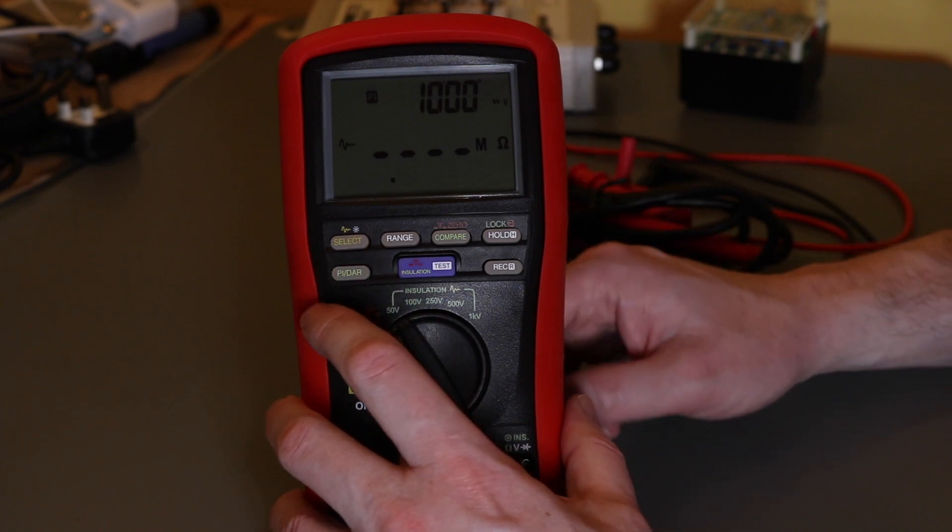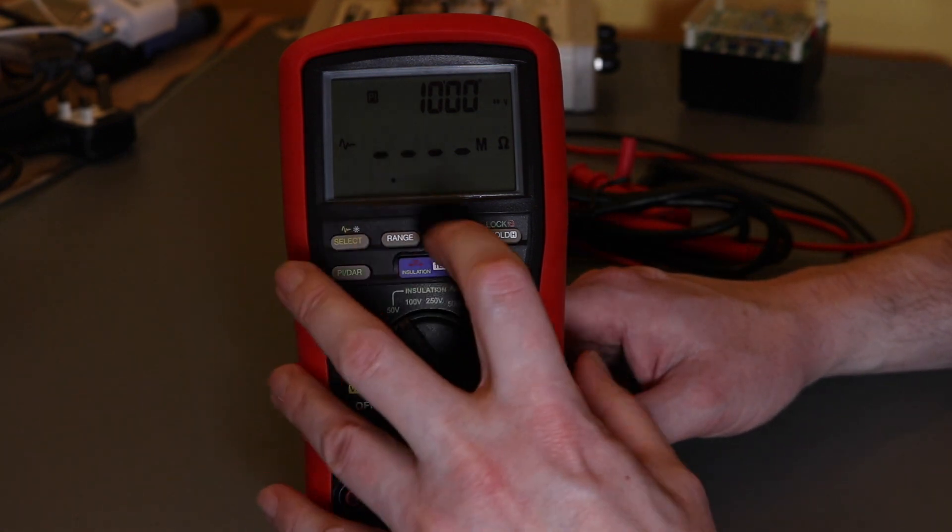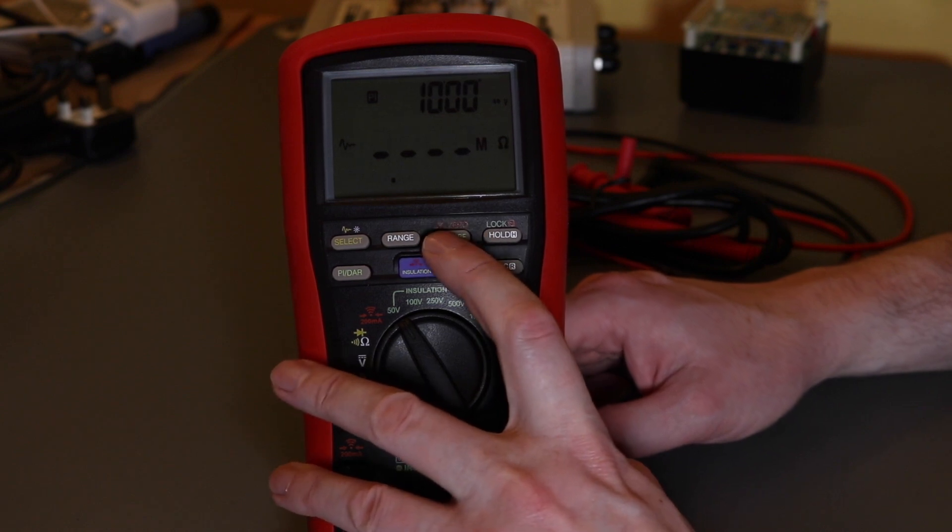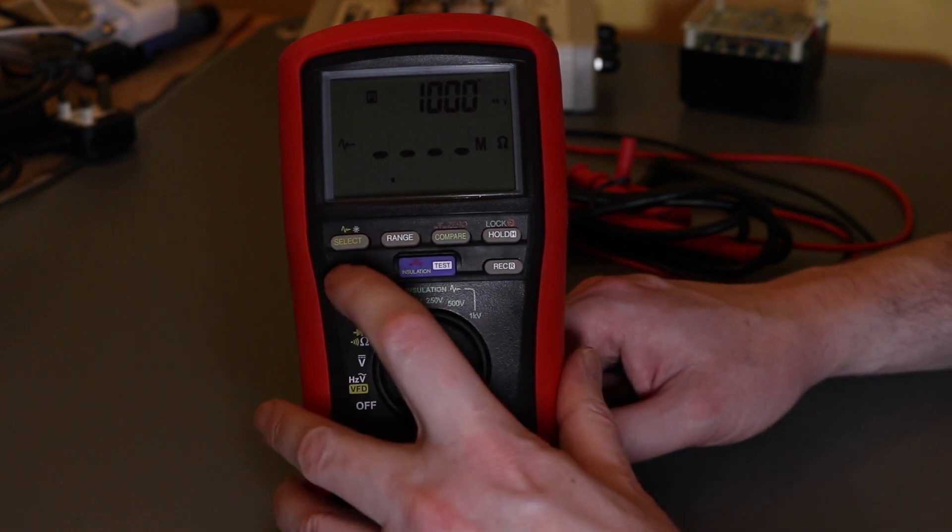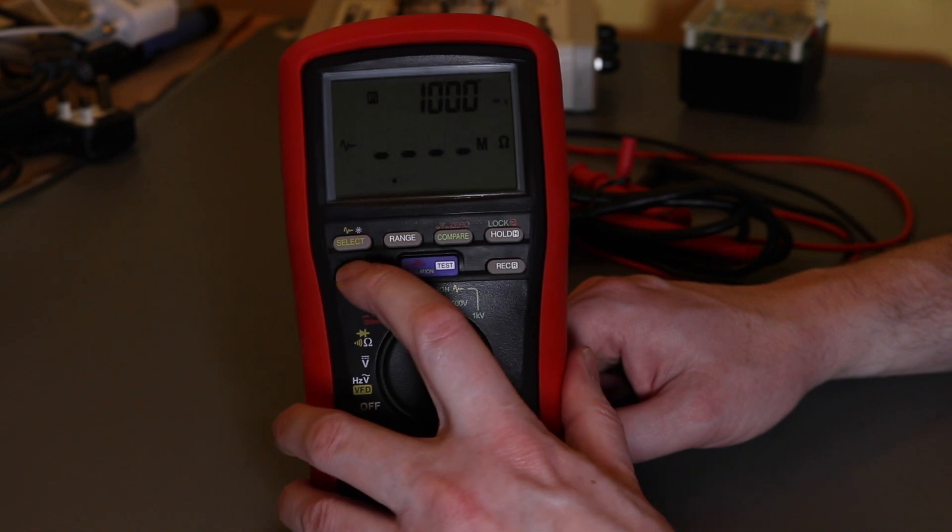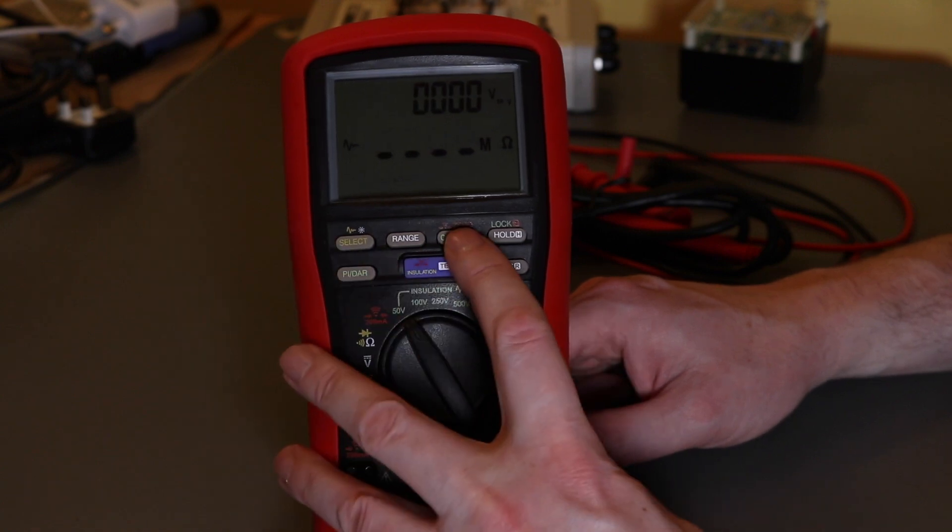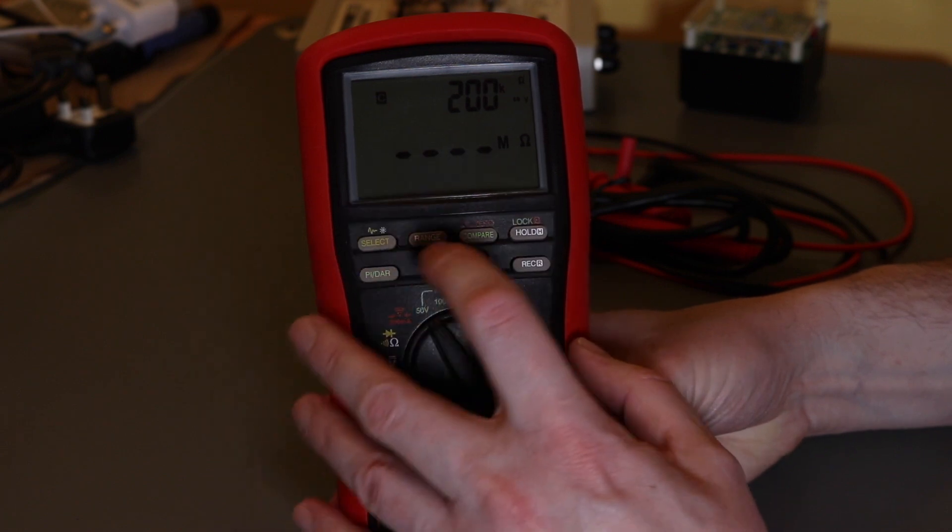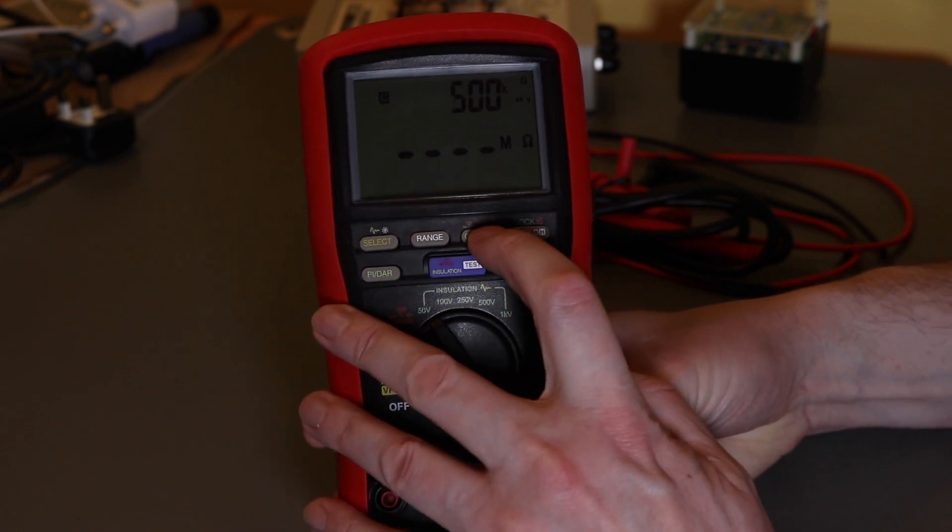You also have in insulation test modes a compare function that you can't do when you're on PI and DAR. So get rid of those and you hit that button once and it brings up the previous value. It's set to 200M ohm on this, and you just keep pressing the button to select predefined values.